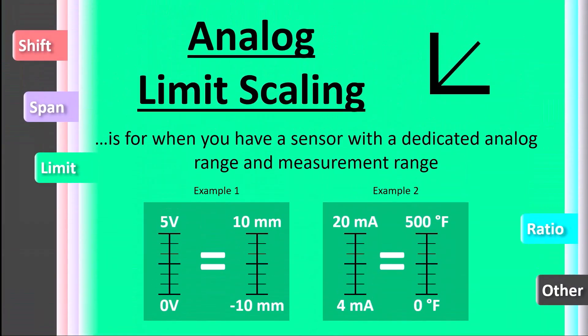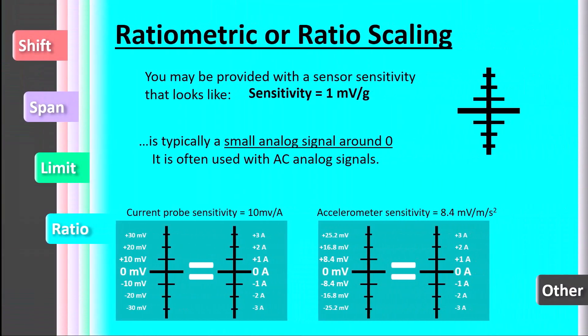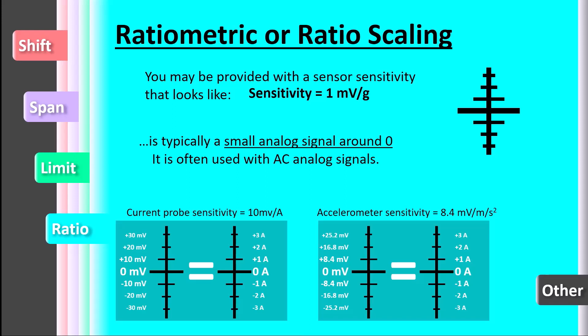The last type of scaling is called ratiometric or ratio scaling. This type of analog scaling is typically used for signals expected to have small vibrations around a zero point. Specifications for this type of scaling will either assume that both values will align at zero or ask to perform a calibration shift after measuring.